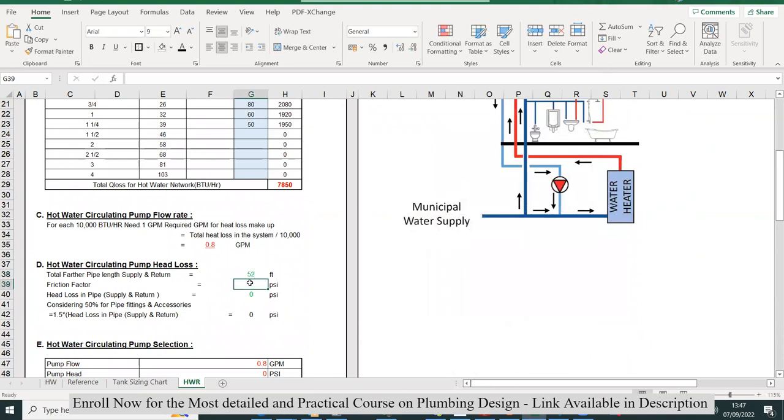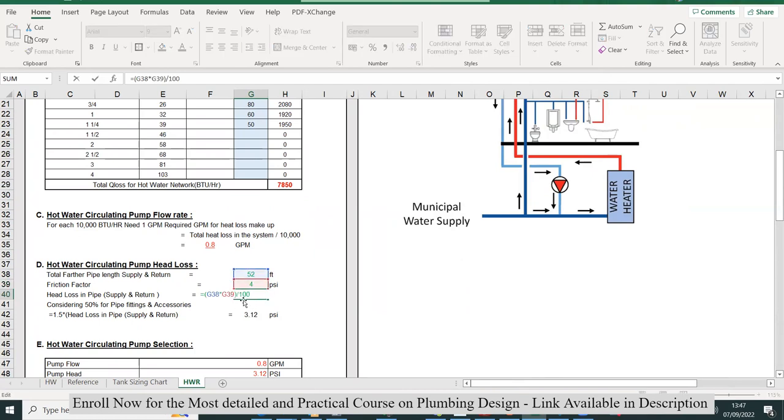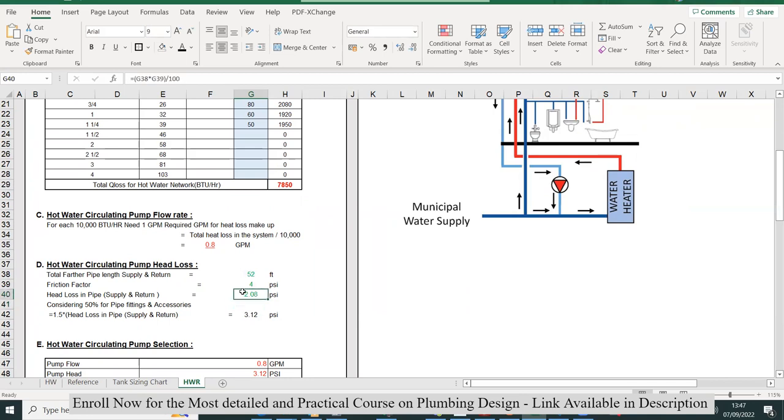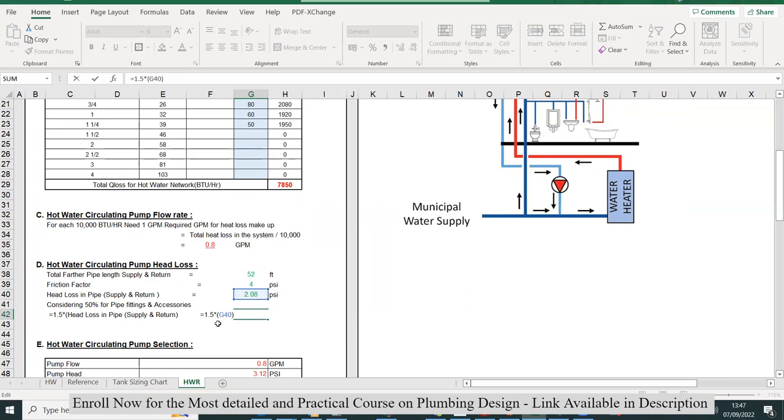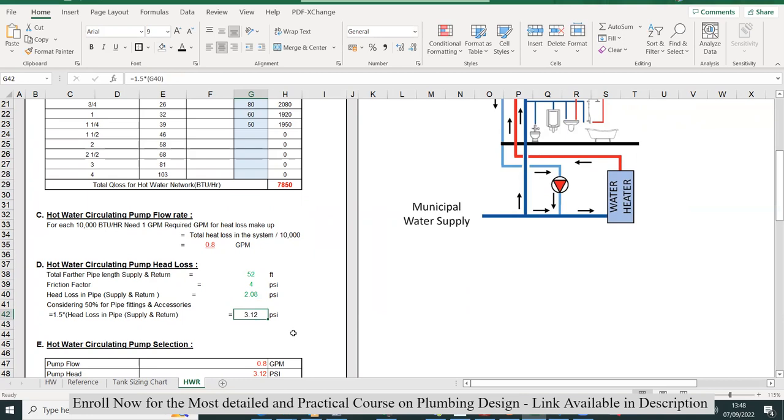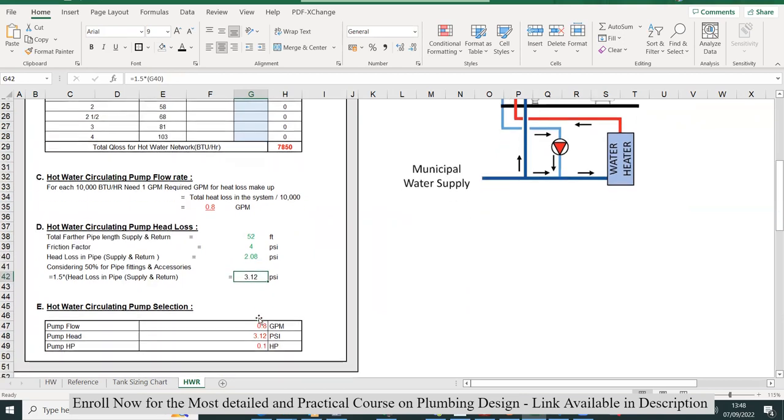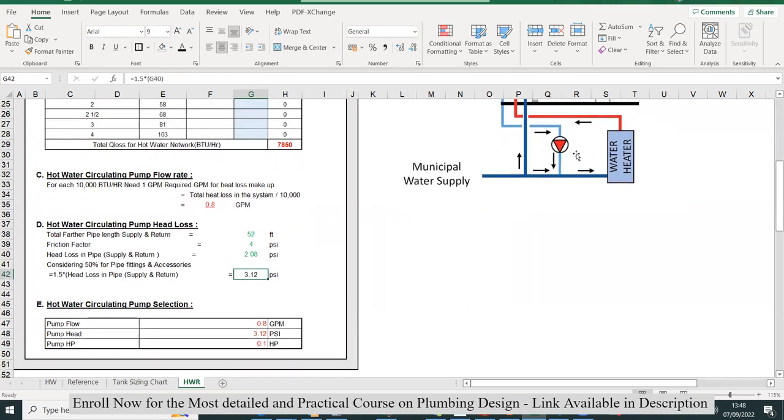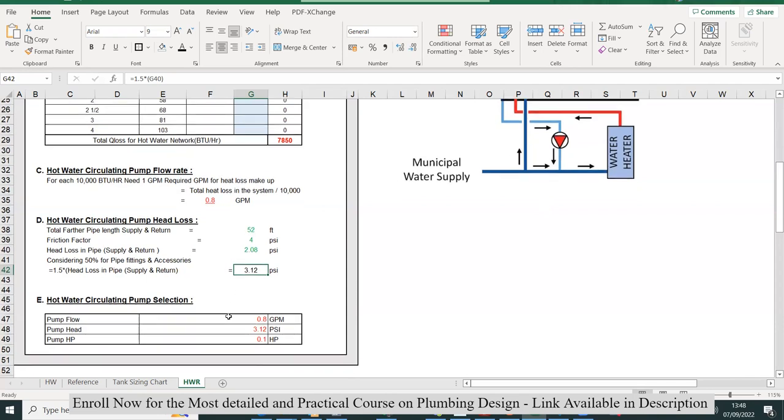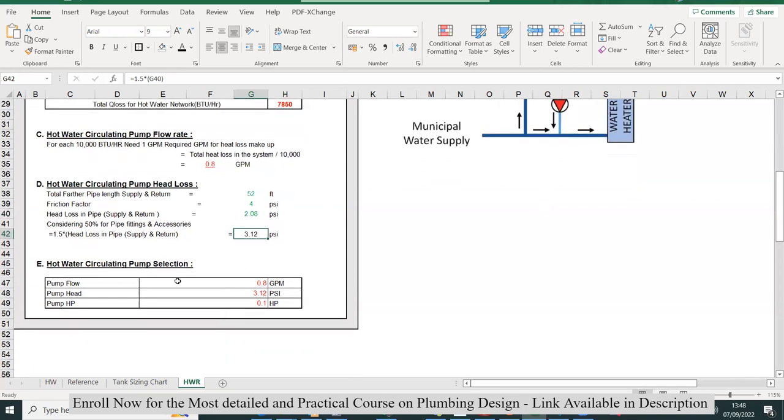For the friction factor, we usually design these domestic pipes in the range of 4 to 5 PSI, so I'll write 4 PSI here. You'll get the value: friction head loss divided by 100 gives you the friction losses in pipes. For fittings and accessories, I'll take 50% of the pipe length, so 1.5 multiplied by the head loss in the pipe supply and return. That's 3.12 total head loss for this pump.